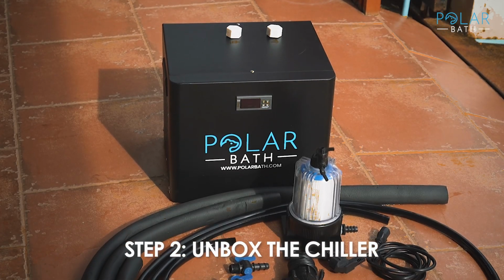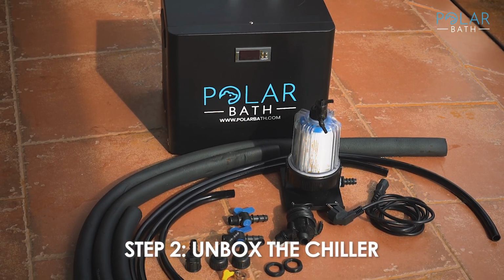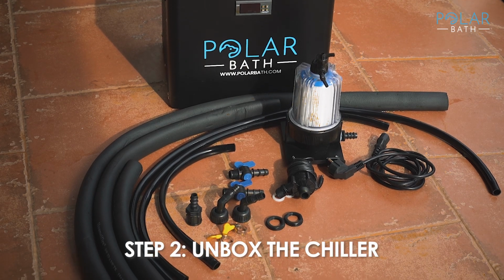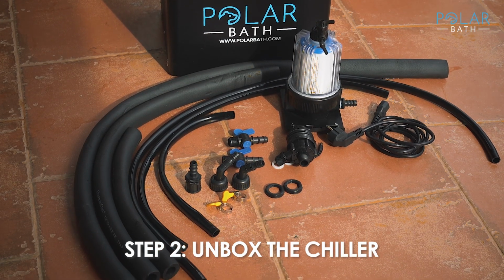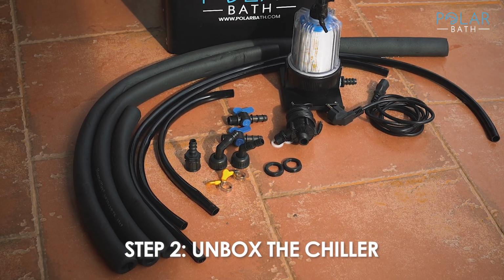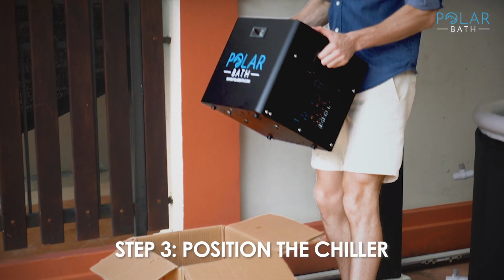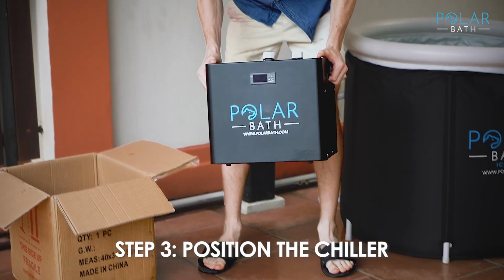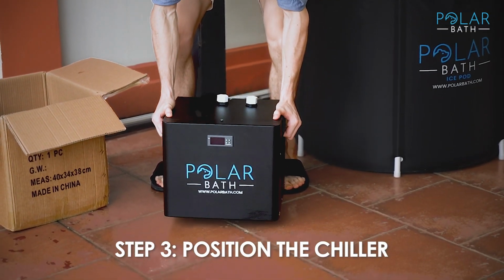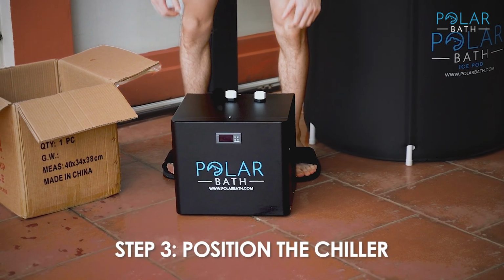Unbox your pod chiller and check that you have all the parts: the chiller unit, power cable, water filter, hose connectors, extra seal rings, and Teflon tape. Place the pod chiller next to your PolarBath, making sure there's at least 15 inches of space around it for proper airflow. It should be on the same level as the ice bath.